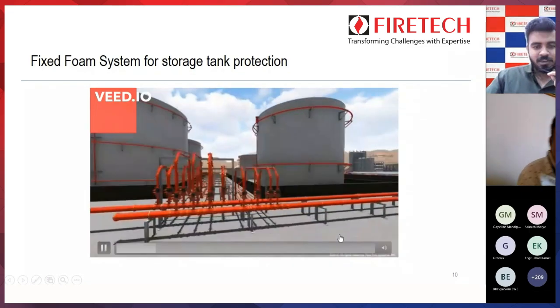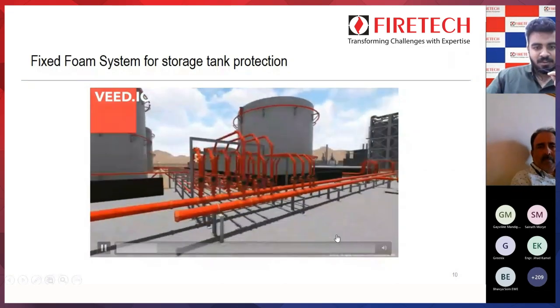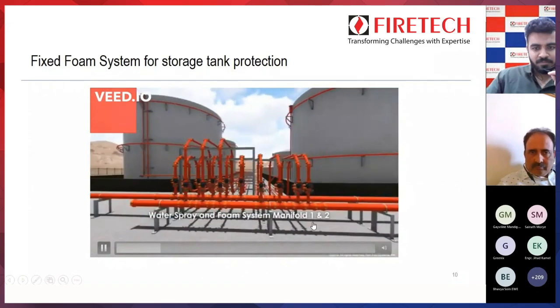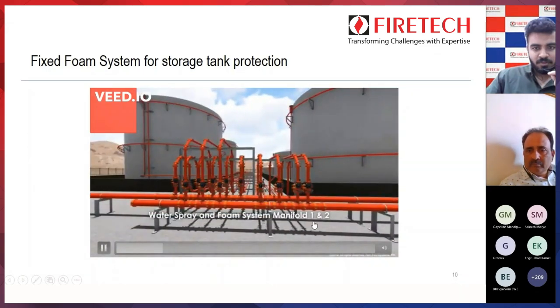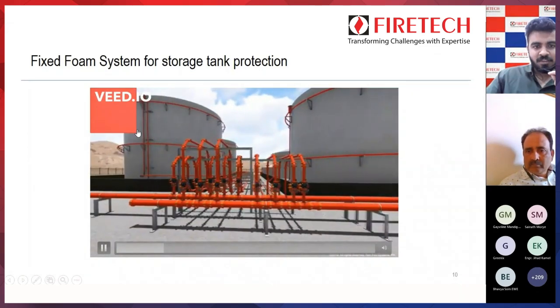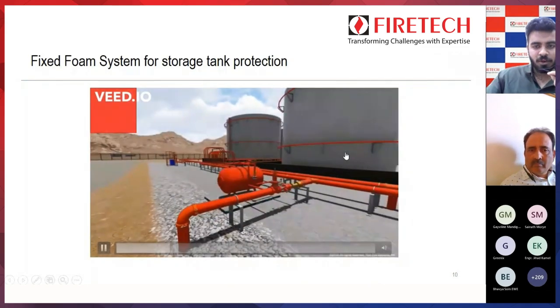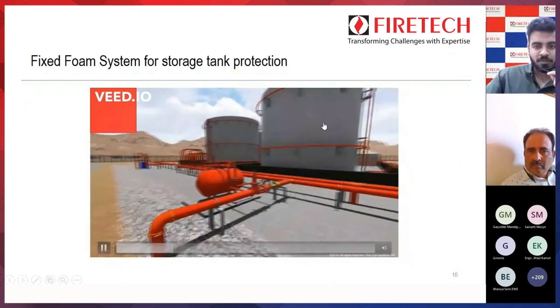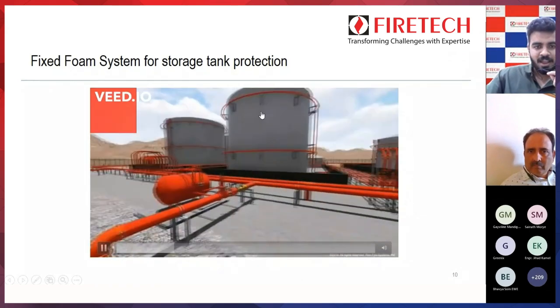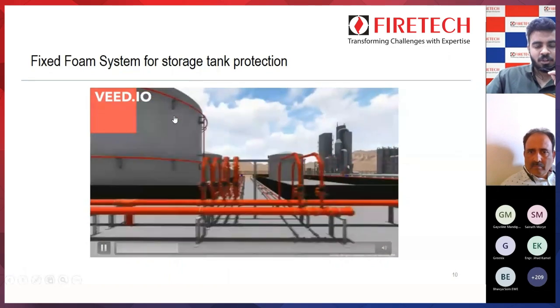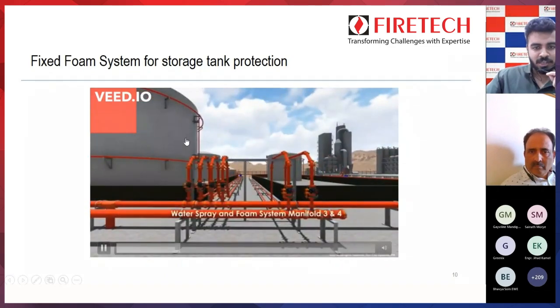This is a bladder tank over here. For the storage tank, along the periphery we are using MV nozzles for secondary protection — that is only for the cooling purpose of the tank. Your primary protection is your foam chamber or makers which have been mounted over the storage tank.